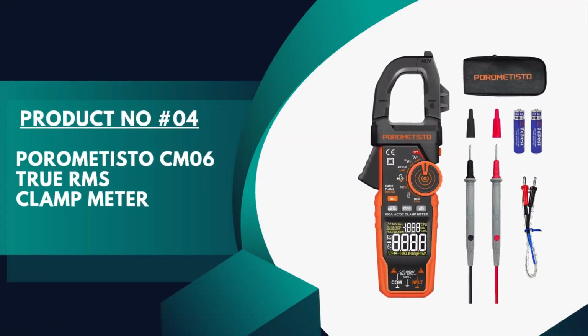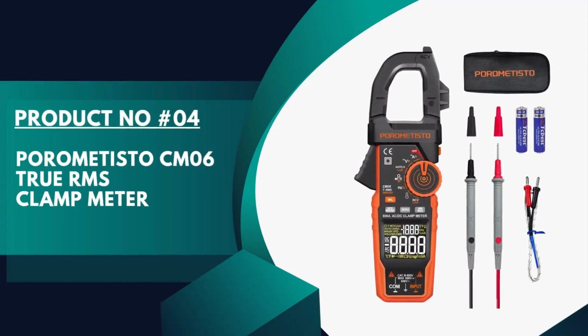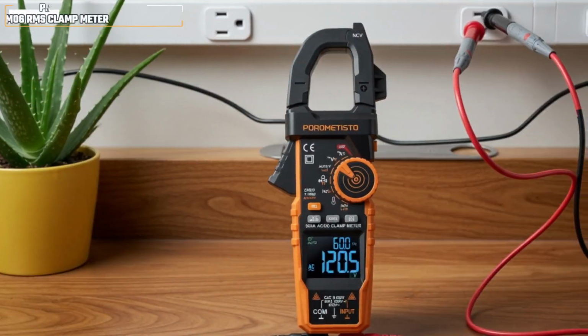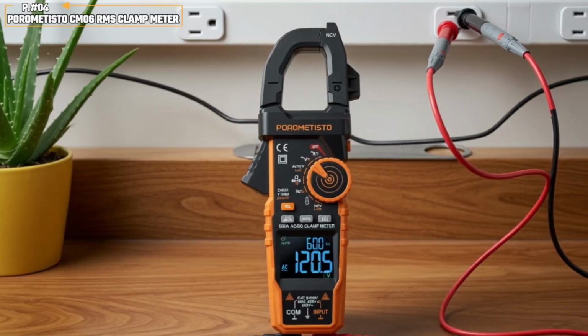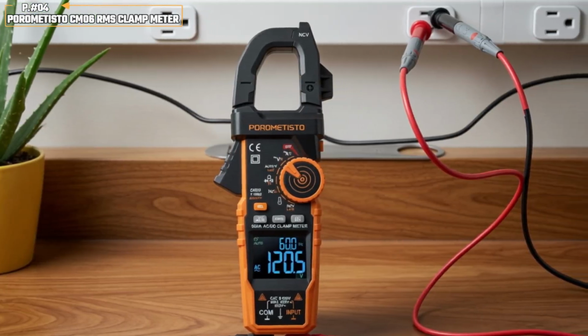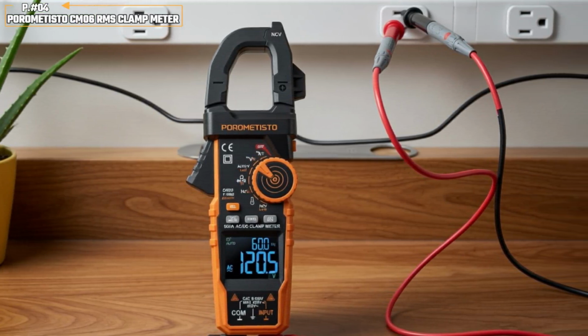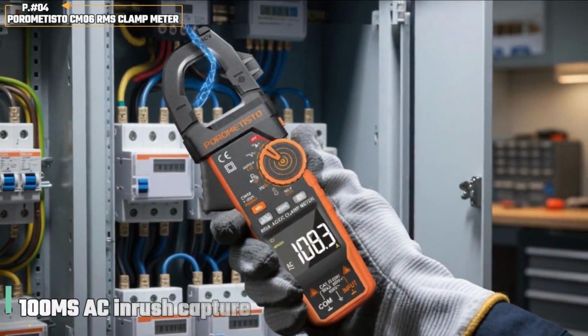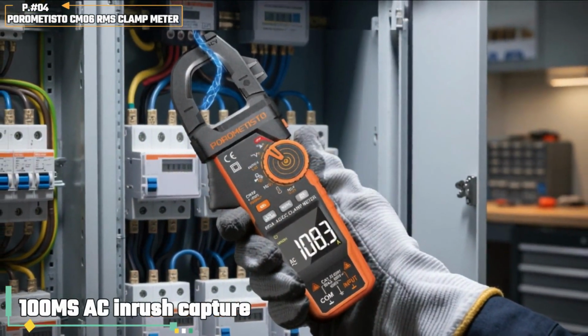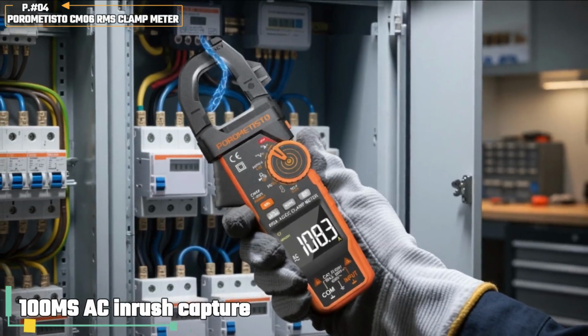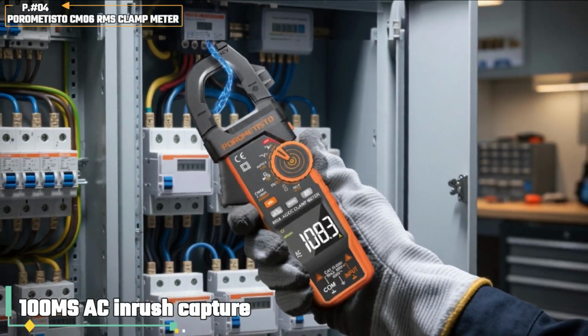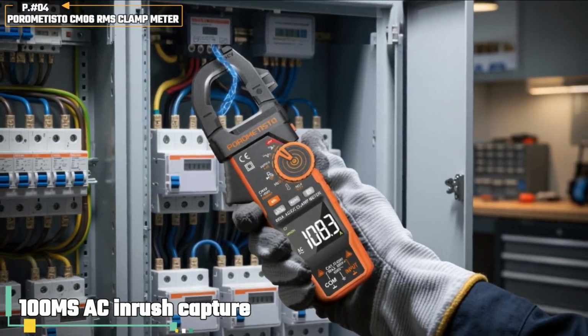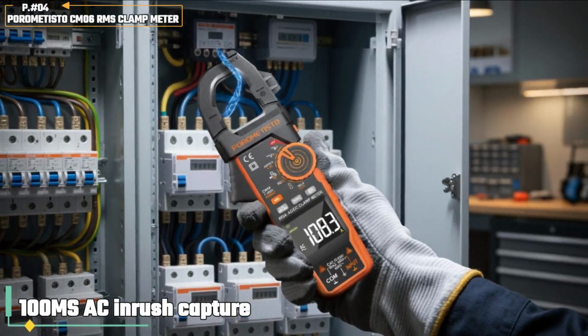At number 4, the Porometisto CM06, our inrush specialist for motors and compressors. This is a strong choice for HVAC work, motor testing, and anyone who needs more diagnostic control than a basic clamp meter provides. Its standout feature is AC inrush current capture. The meter records the startup surge over approximately 100 milliseconds, helping you investigate motors, pumps, and compressors that trip breakers during startup.